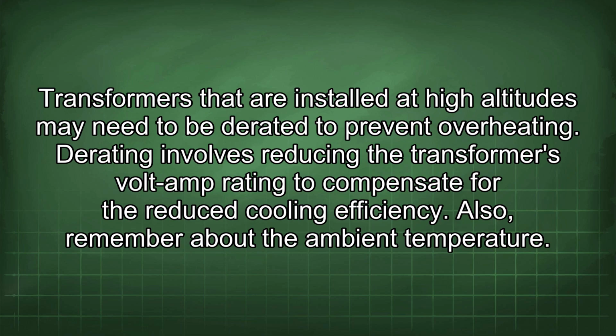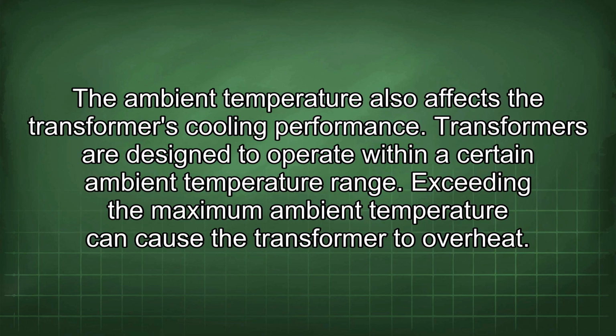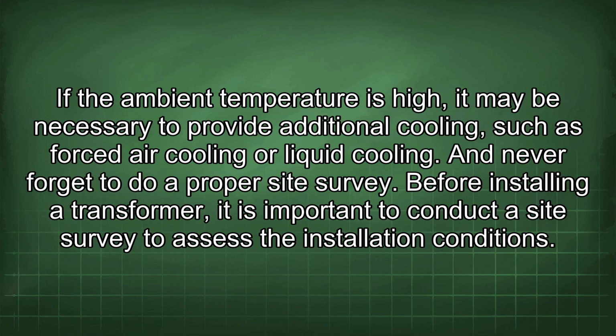Also, remember about the ambient temperature. The ambient temperature also affects the transformer's cooling performance. Transformers are designed to operate within a certain ambient temperature range. Exceeding the maximum ambient temperature can cause the transformer to overheat. If the ambient temperature is high, it may be necessary to provide additional cooling, such as forced air cooling or liquid cooling. And never forget to do a proper site survey.